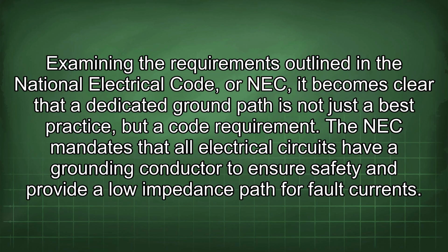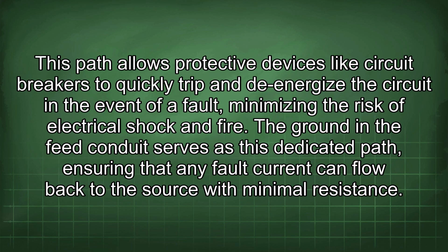The NEC mandates that all electrical circuits have a grounding conductor to ensure safety and provide a low impedance path for fault currents. This path allows protective devices like circuit breakers to quickly trip and de-energize the circuit in the event of a fault, minimizing the risk of electrical shock and fire. The ground in the feed conduit serves as this dedicated path, ensuring that any fault current can flow back to the source with minimal resistance.